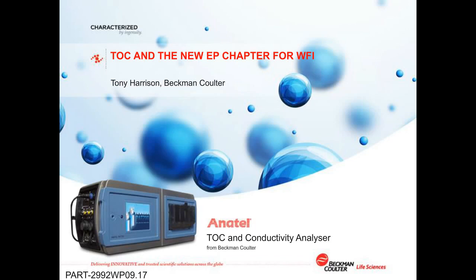However, as I've mentioned, if you see a change to the TOC levels combined with a change of the oxidation profile, which the PAT 700 will report to you, that's a good indication that there's a change to the organic chemistry in the water system, and certainly an indication that more in-depth investigation could be required.